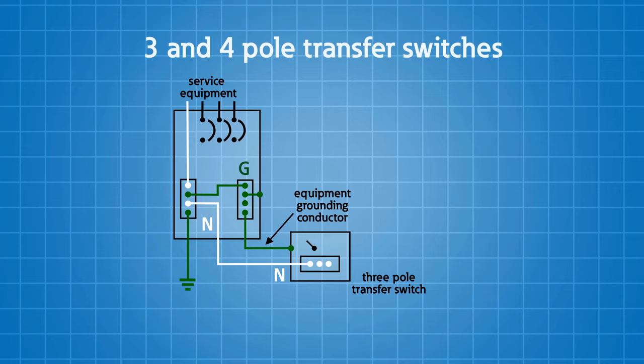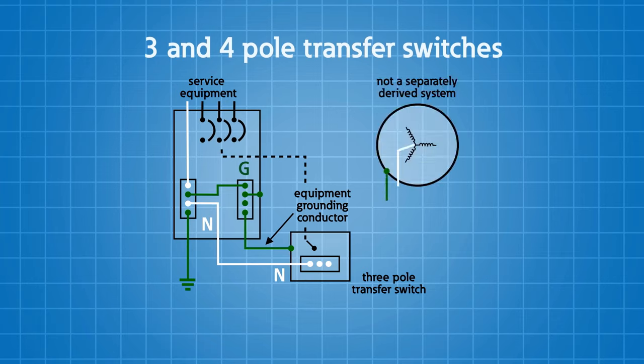You'll have a feeder come off of your panel board and feed the transfer switch. On the other side of that transfer switch, we have a generator. The generator will be connected directly to the transfer switch, obviously through some overcurrent protective devices. And then your transfer switch is going to supply loads. So this is a basic layout of a transfer switch with a generator in a system.